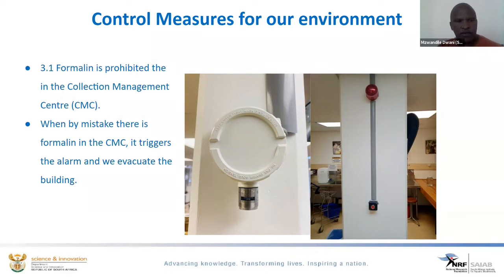These are control measures that we are using for our environment at SAIAB. We are trying by all means to eliminate the formalin in the CMC, because CMC is where we are working, and then we expect to only have propanol and ethanol. Hence, if you can look on the left, this is the formalin sensor. If the readings of the formalin are above 0.75 ppm, this will trigger the alarm and immediately we will evacuate the building for 1 to 2 hours.